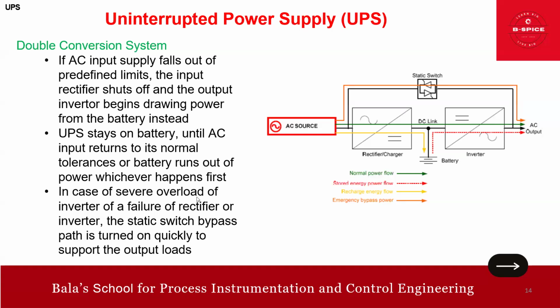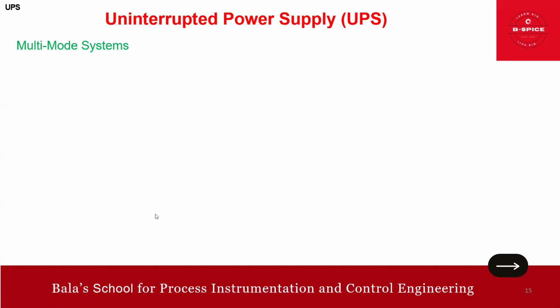In case of a severe overload of the inverter, or failure of the rectifier or inverter, the static bypass switch is turned on to quickly support the output load. You got it, friends? If anything overload happens here, the static bypass switch will turn on to support the output load. So this is about double conversion.